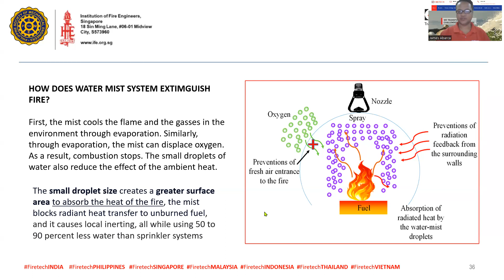Okay, so FOGTEC, in partnership with Partech, has different applications. It can be a wet system. In a wet system, the pipework is permanently filled with water, same principle as sprinkler, and kept at a standby pressure with a pressure maintaining device, which is the jockey pump. Almost the same principle, but this one is high pressure. Pre-action systems are dry systems which are used in combination with an external fire detection system. So there is an activation system for this so that it will activate the pre-action valve.